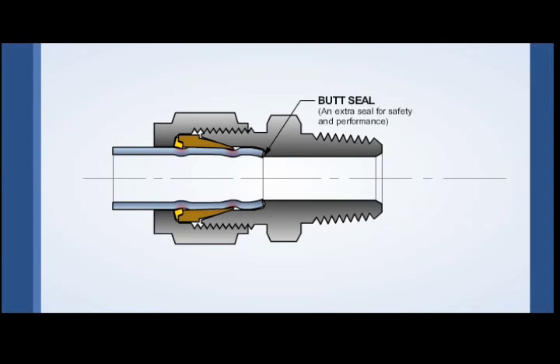The butt seal also prevents potentially corrosive process fluid from entering the area between the outer tube wall and the fitting body, often referred to as a dead leg. Avoiding a dead leg prevents areas of low flow and low concentration, which play an active role in the corrosion process.